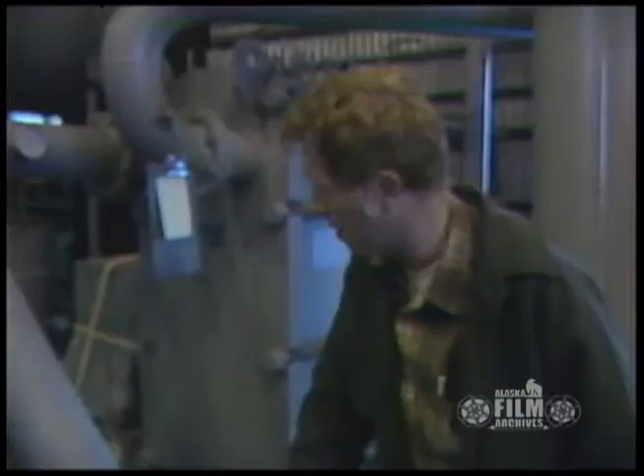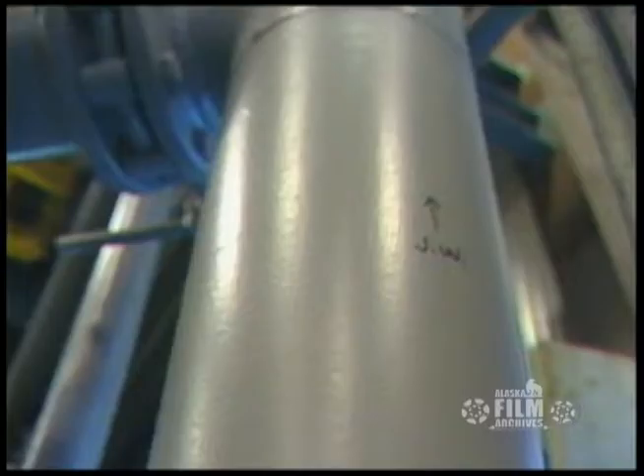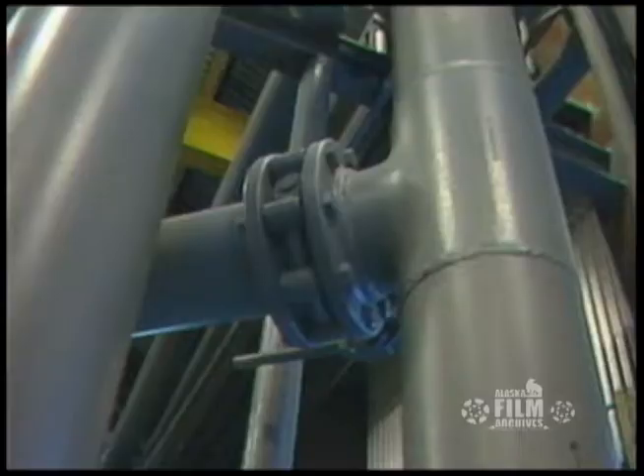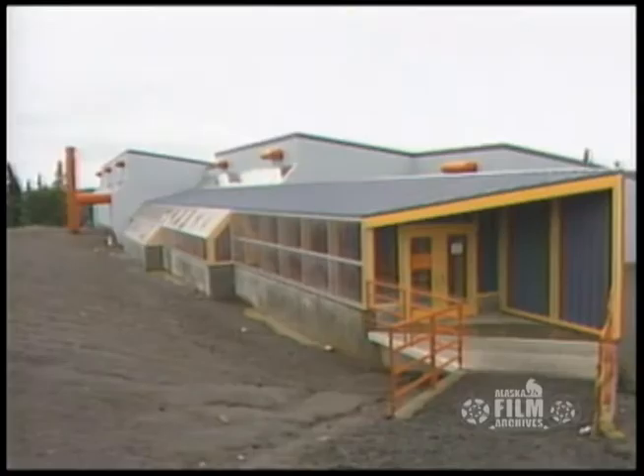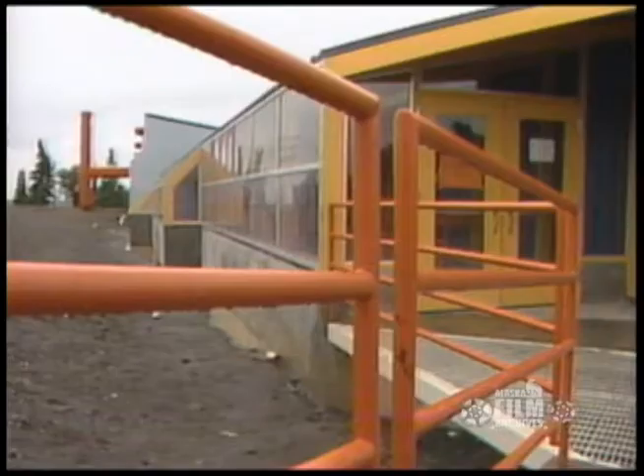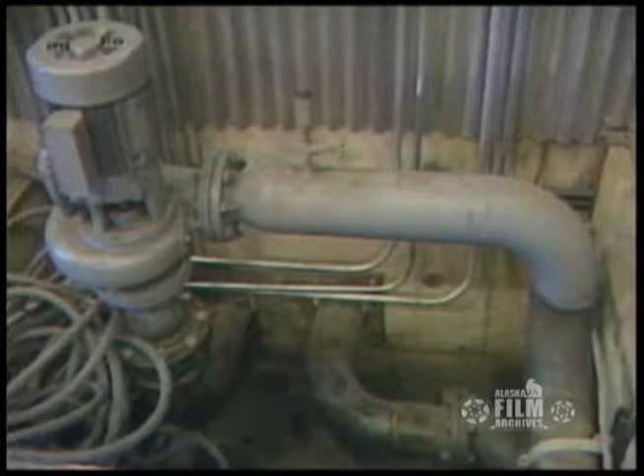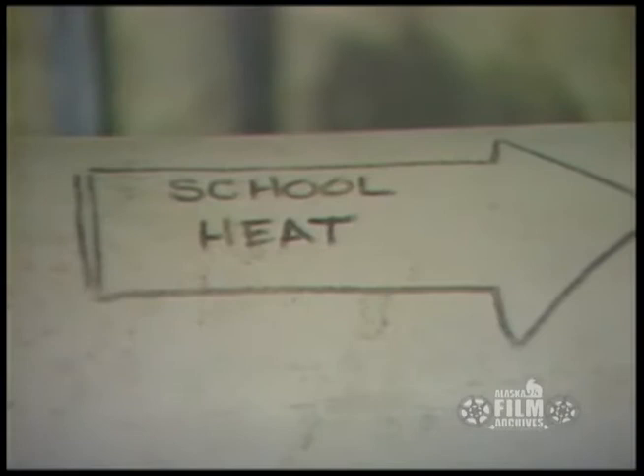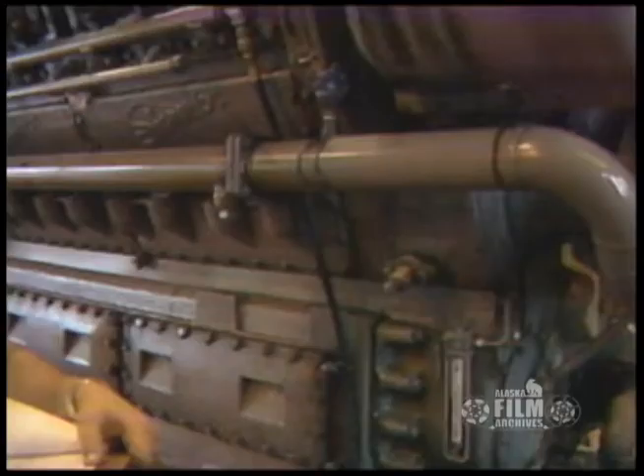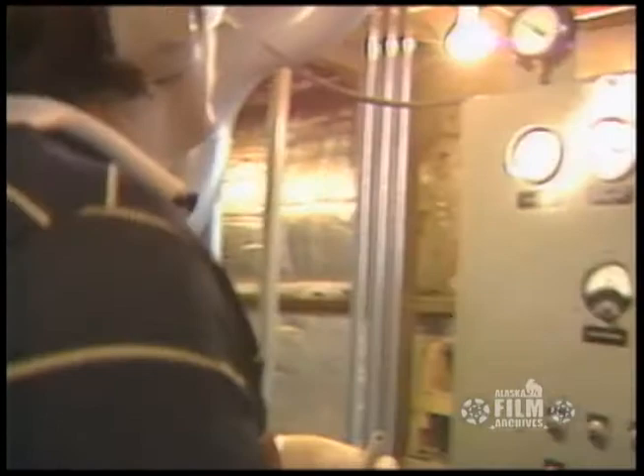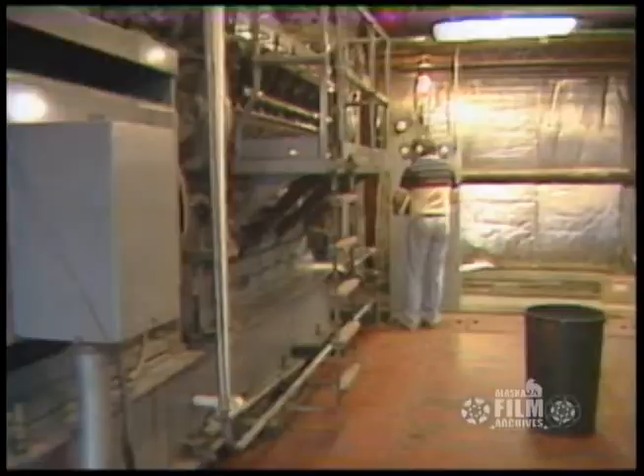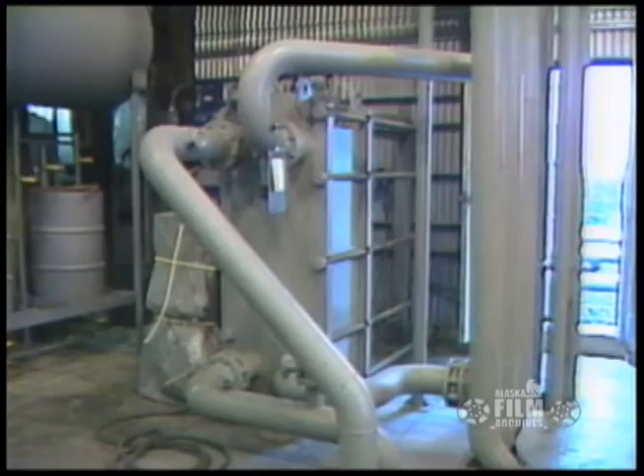Since approximately the 1st of January, we've delivered about 440 million BTUs of waste heat to the grade school, which has offset about 5,000 gallons of stove oil. This probably reflects an offset of about $6,000 in fuel costs or thereabouts. We plan on expanding the system to the courthouse, to the high school, to the Southwest Region Schools facility, and also the state highway department complex.